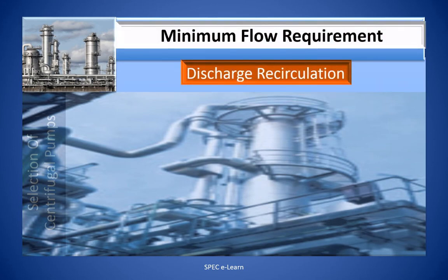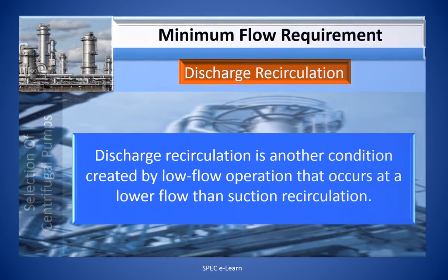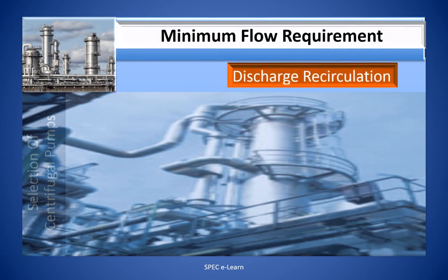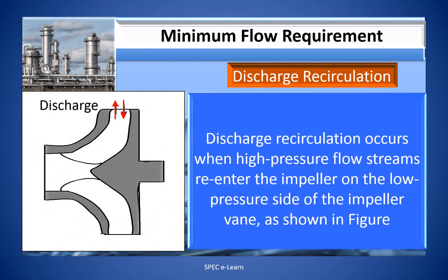Another problem at low flow is discharge recirculation, which is created by low flow operation occurring at a lower flow than suction recirculation. Discharge recirculation occurs when high-pressure flow streams re-enter the impeller on the low-pressure side of the impeller vanes. The reverse flow within the impeller passage shears across outgoing flow, producing vortices along the pressure wall and causing cavitation along the pressure wall and shrouds adjacent to the impeller outlet.